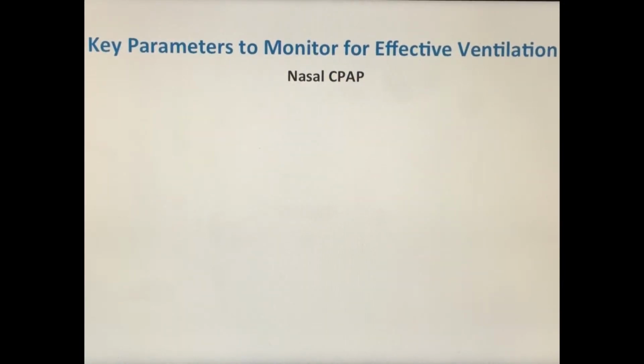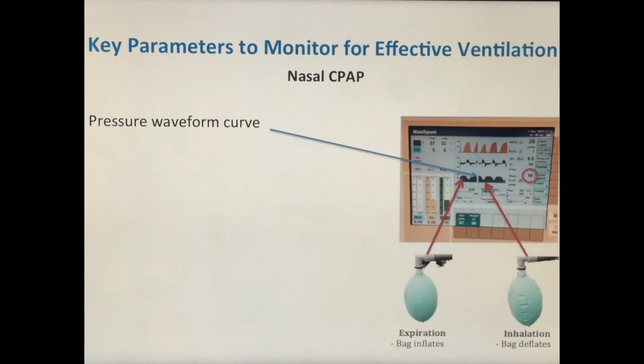The next parameter that we want the clinician to monitor is the pressure waveform curve, which is seen on the anesthesia machine, shown here. The pressure waveform curve lets us measure the pressure during expiration and inspiration. It also lets us know that the patient is maintaining effective and spontaneous ventilation. Let me show you how. On expiration, you'll notice that the bag will inflate. This is because the patient is exhaling into the bag. It correlates with the plateau on the pressure waveform curve.